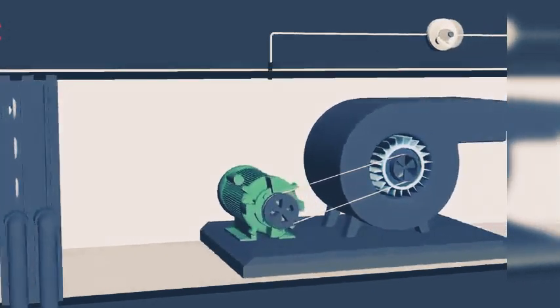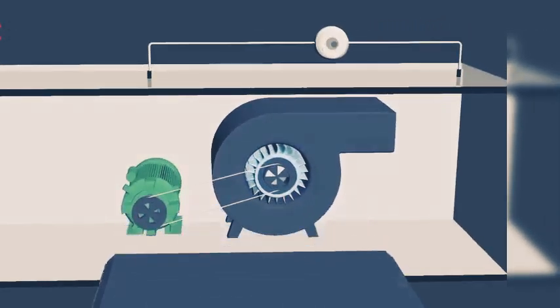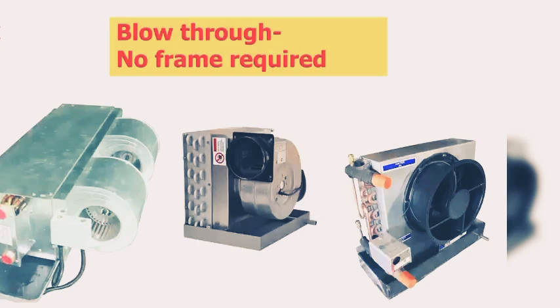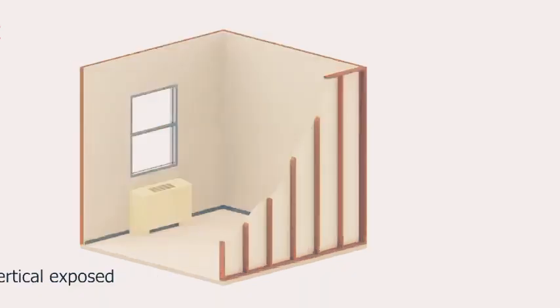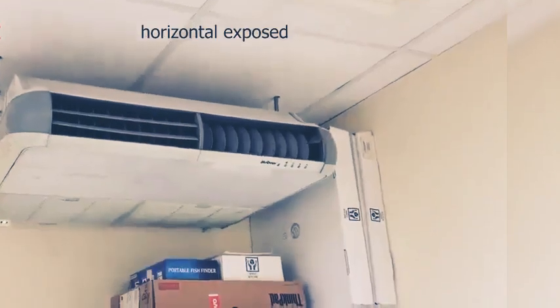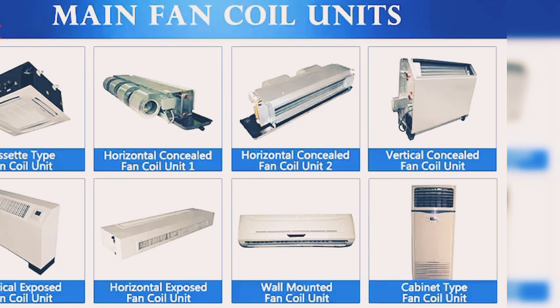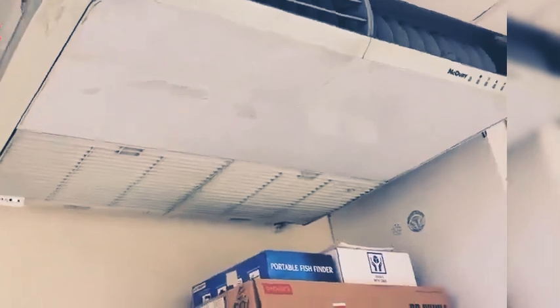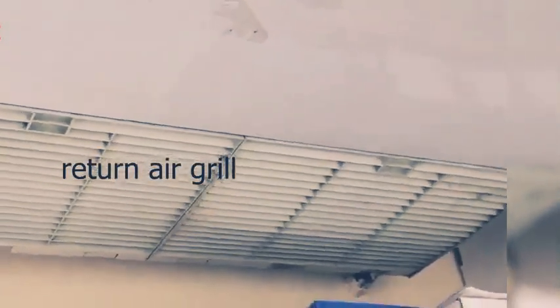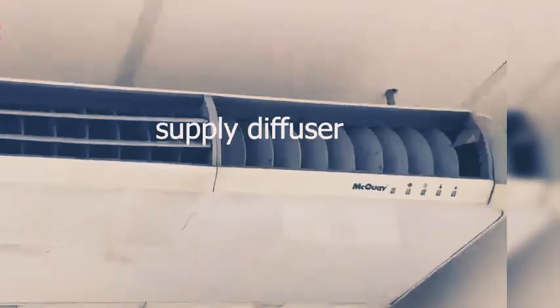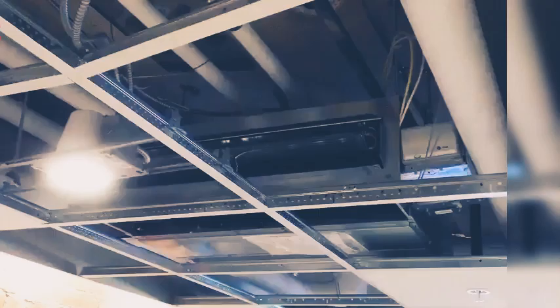However, they are more expensive, as they require a chassis to hold the fans, whereas a blow-through unit typically consists of a set of fans bolted straight to a coil. A fan coil unit may be concealed or exposed within the room or area that it serves. An exposed fan coil unit may be wall-mounted, freestanding, or ceiling-mounted, and will typically include an appropriate enclosure to protect and conceal the fan coil unit itself, with return air grill and supply air diffuser set into that enclosure to distribute the air. A concealed fan coil unit will typically be installed within an accessible ceiling void or services zone.